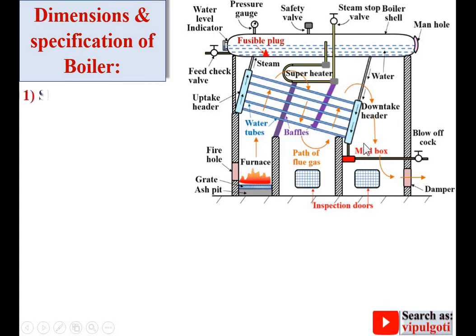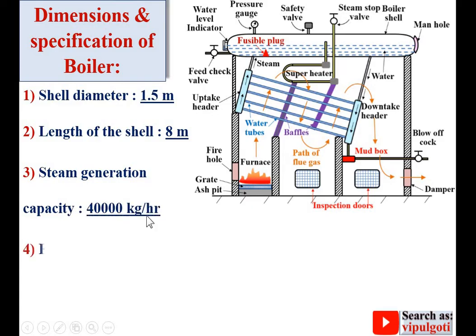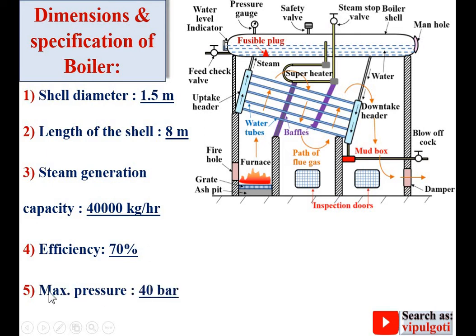The dimensions and specifications of the Babcock-Wilcox boiler: shell diameter is 1.5 meters, length of the shell is 8 meters, steam generation capacity is 40,000 kg per hour, efficiency is approximately 70 percent, and the maximum pressure of the steam is 40 bar. This is the typical specification of the Babcock-Wilcox boiler, but it can vary slightly.